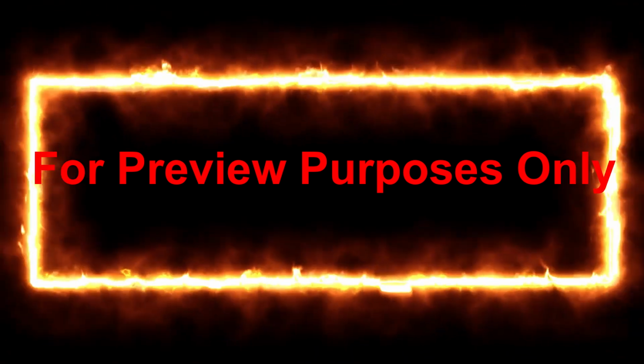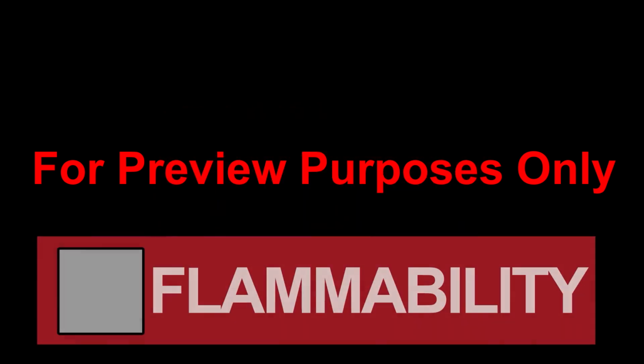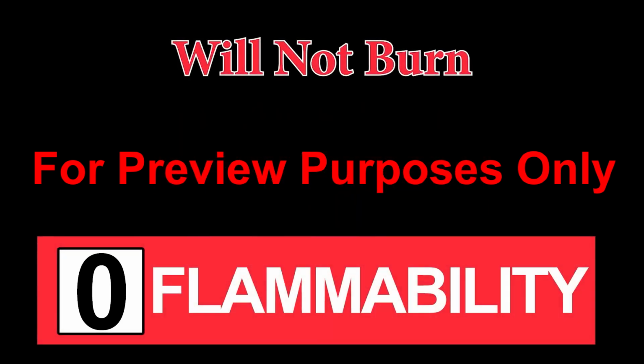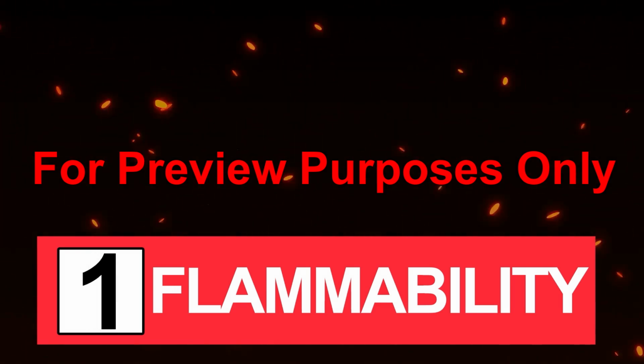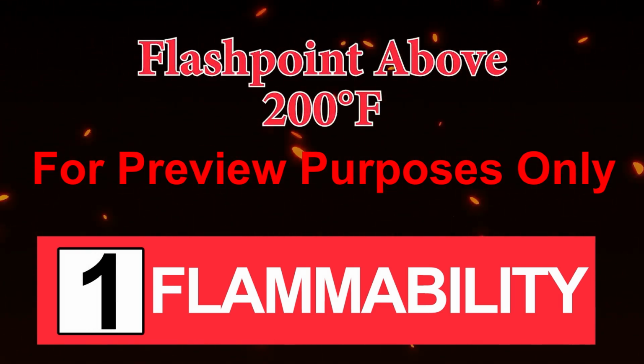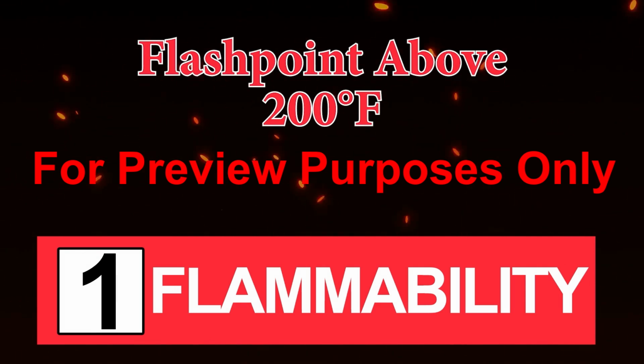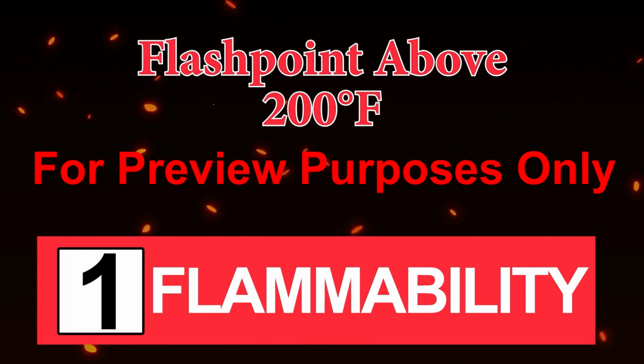In the flammability category, materials are labeled depending on their flash point, which determines how likely they are to burn. Materials that will not burn at all are labeled with a 0, while a 1 represents materials with flash points above 200 degrees Fahrenheit, which are difficult to ignite. They must be preheated to burn.